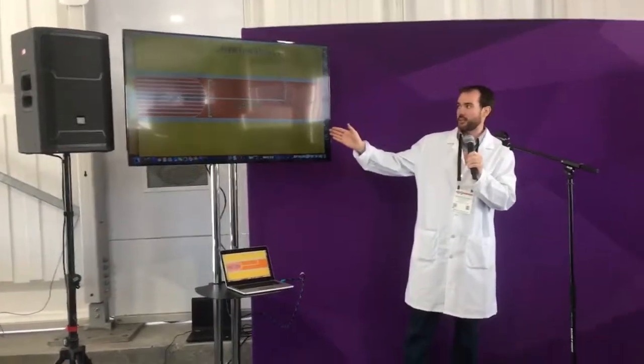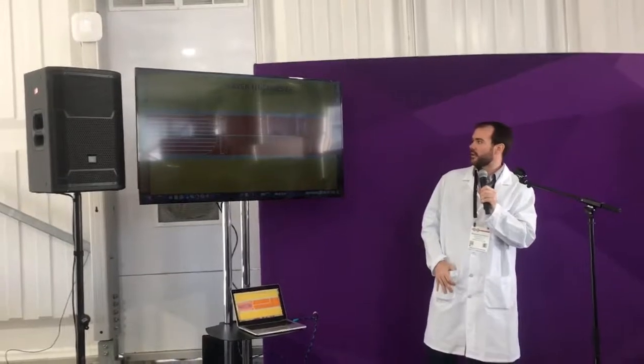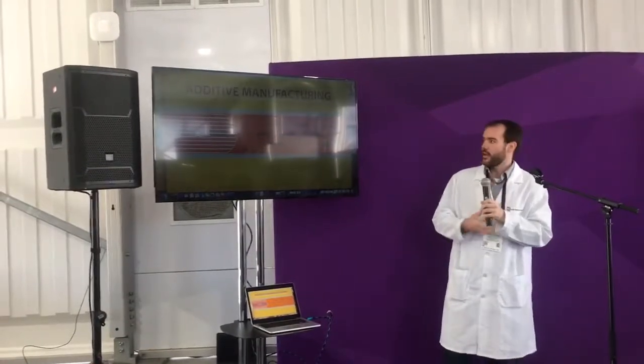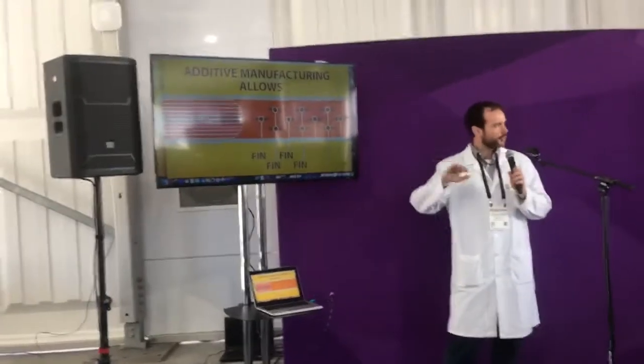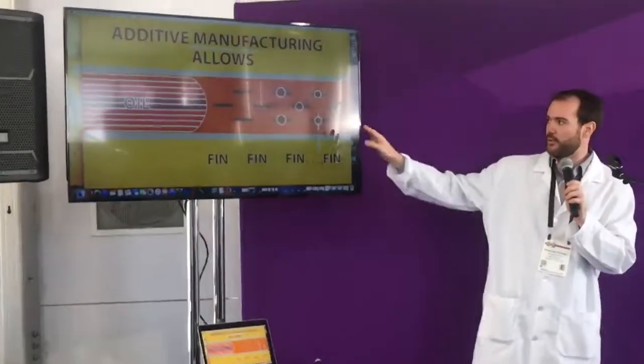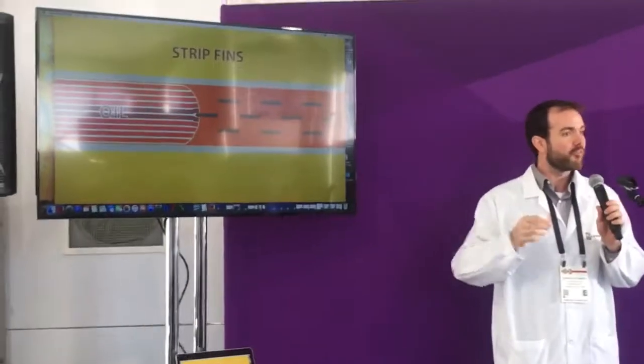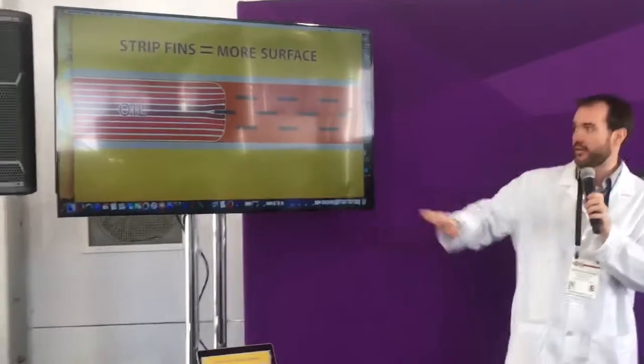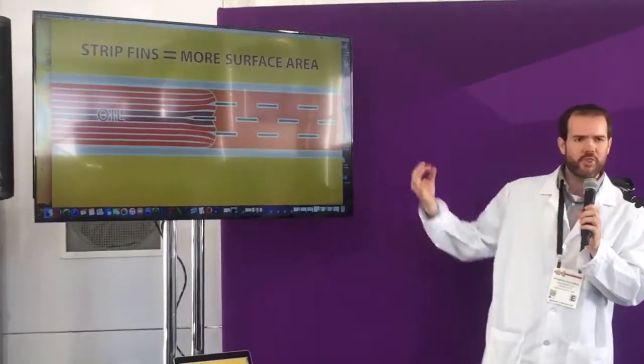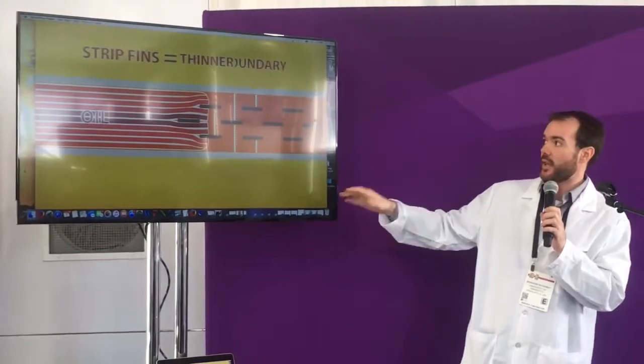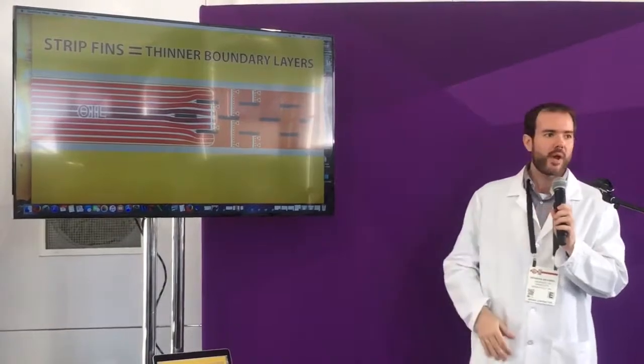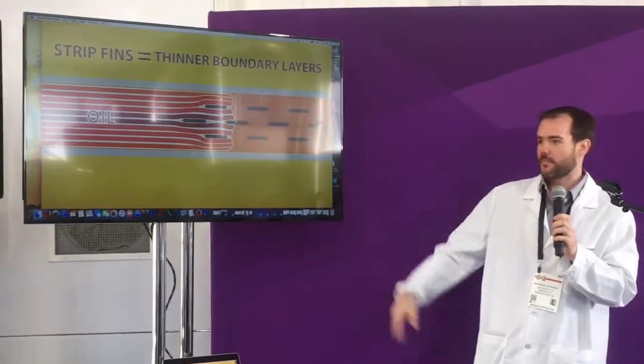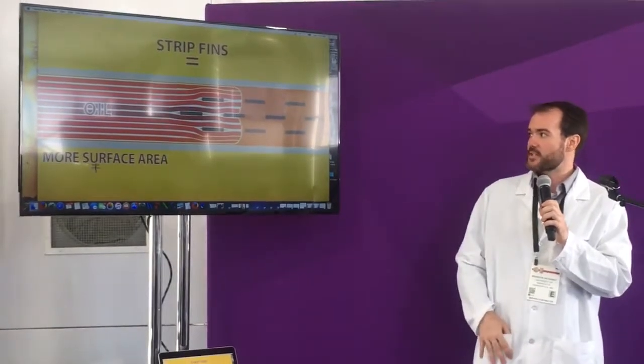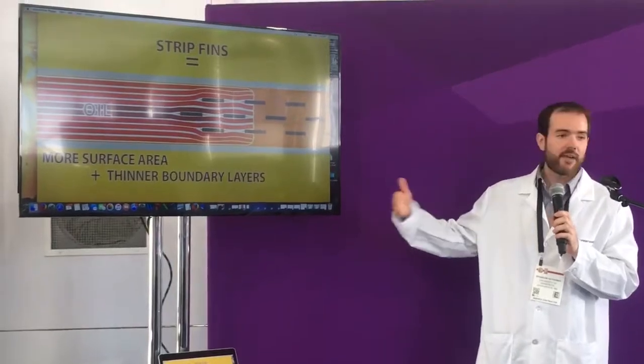A traditional tube with no internal offset strip fins tends to have difficulty in moving the heat to the edge of the system. Now what we've included are a series of fins that will be introduced next. There they are. These were printed directly inside the tubes, and the tubes are a shaped tube, so traditional brazed inserts that would be used to include a feature like this wouldn't be functional with a shaped outer tube. It would be very difficult to include. With 3D printing, we're able to add these features inside our shaped tubes to break up your thick, viscous oil flow to get thinner boundary layers, as well as more surface area inside your tube to more rapidly move the heat from the oil to the walls of your tube. So these offset strip fins, again, provide benefits from the surface area and from the fluid dynamics point of view.